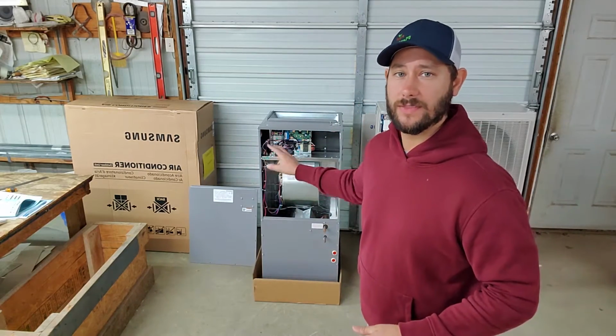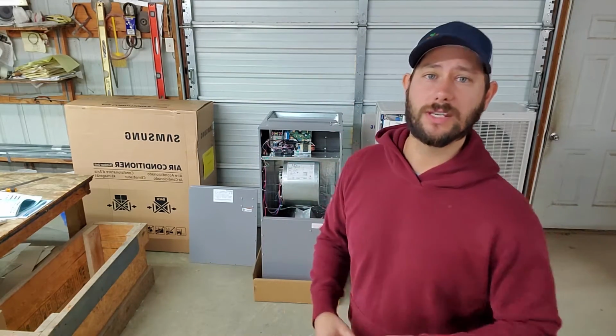All right, let's talk about some other features like the wired controller and option settings, like choosing the indoor sensor on this equipment instead of choosing the wired controller's location. So you have a thermostat in your home and you can choose that as your set temperature. Your thermistor in there controls when it reaches temperature where that thermostat is, then it'll shut the unit off. Now, I've had customers tell me at nighttime, Tad, it gets a little colder than I want. I'd like to keep it a little hotter. Can we do that? I go by their home.